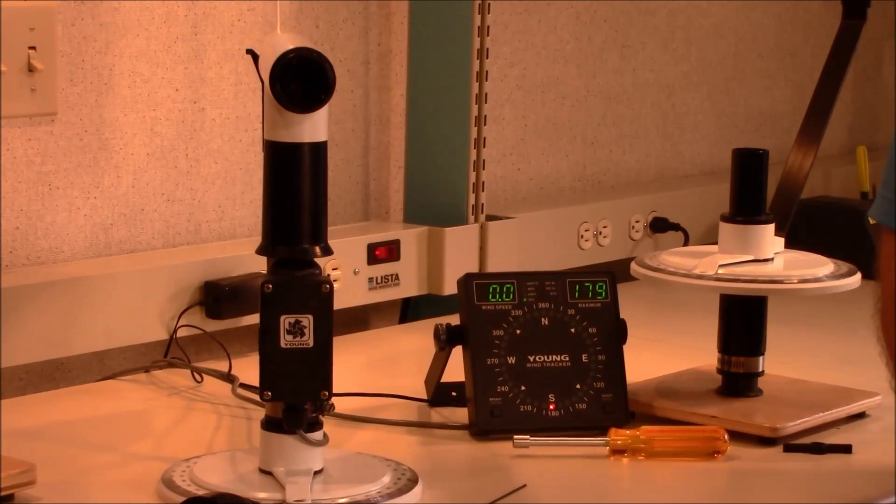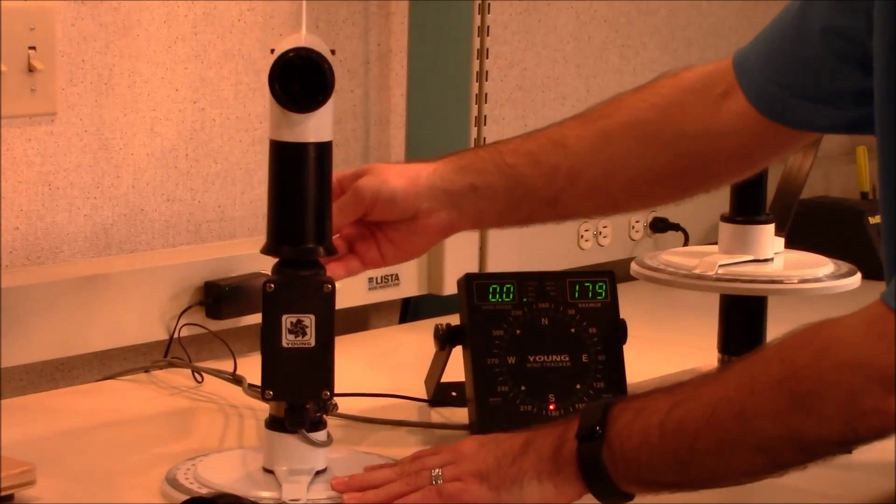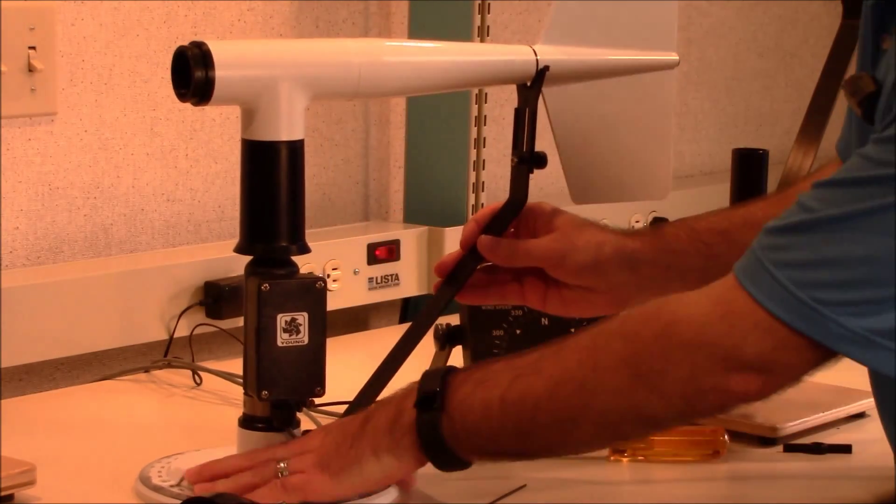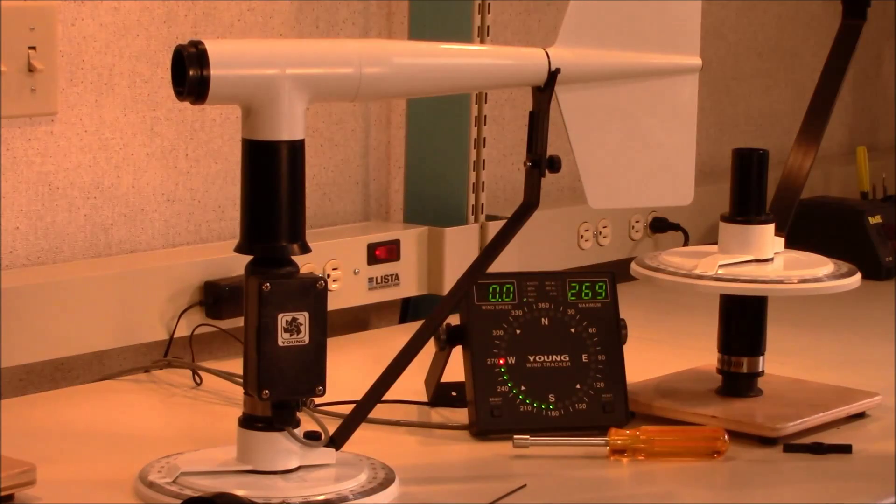We recommend that you check the direction every 30 degrees. For the purposes of this demonstration, I will be checking one more direction. I'm going to set it to 270 degrees, and the display is reading 269, which is within the tolerance.